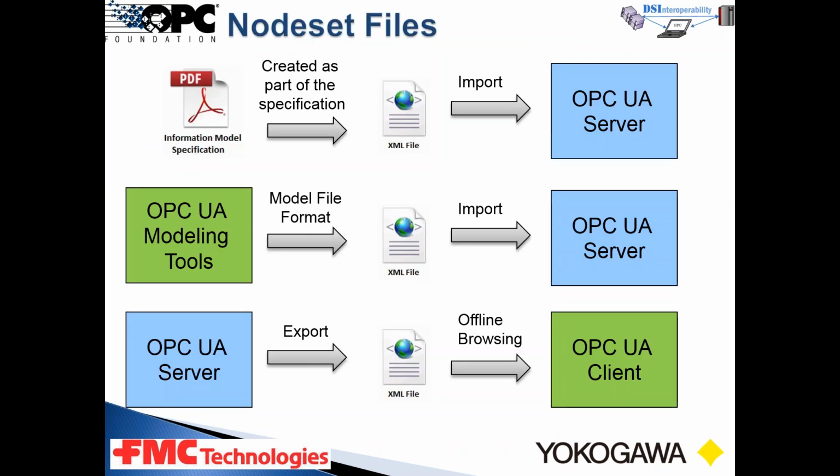Yeah. And a large part of our solution depends upon the node set files. If you see in the current day, the configuration is actually exchanged between the subsea server and the DCS via manually entered Excel files. Now this is actually prone to a lot of errors. So we are actually looking at making use of the node set files.